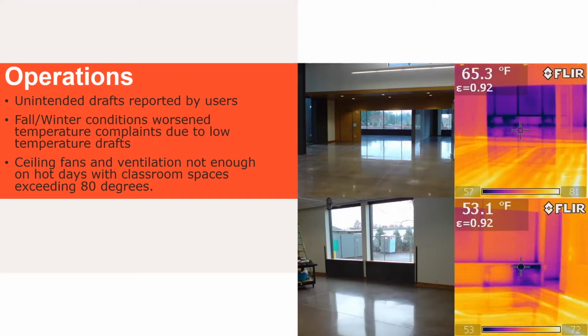Ceiling fans and the ventilation were not enough on hot days, with classroom spaces exceeding 80 degrees. On the southwest side, they literally could not use the spaces by mid to late May, once temperatures really got going. Even at only 78 to 82 degrees, the thermal loading on a sunny day was really starting to impact the spaces, along with the building heating up earlier in the day, earlier in the morning.